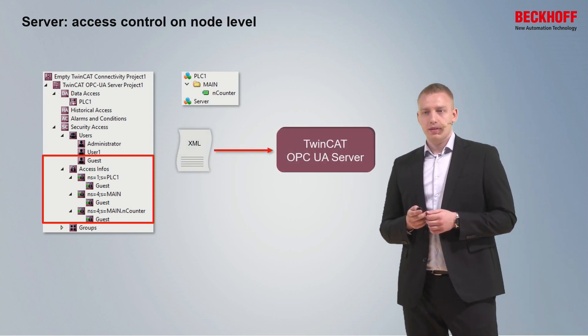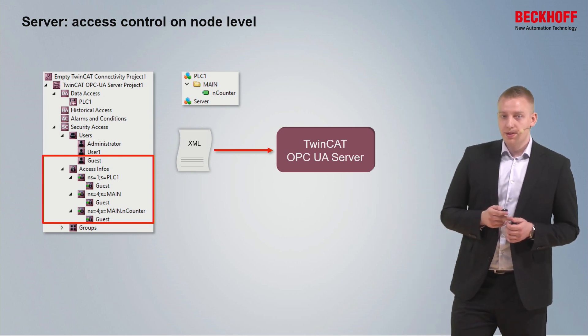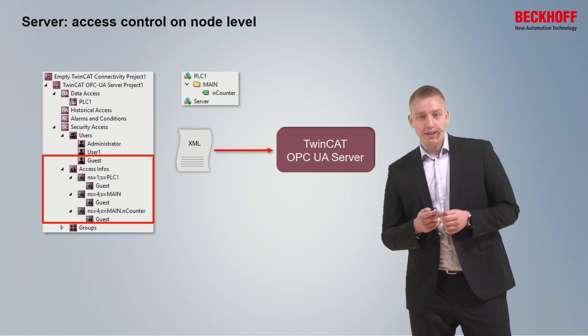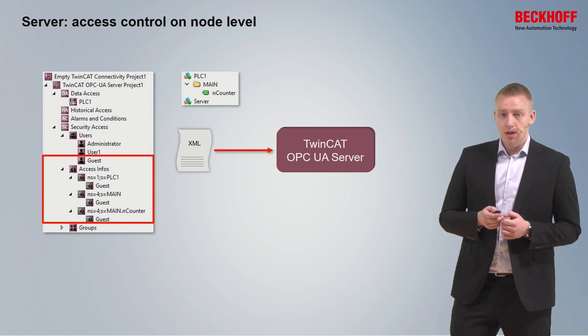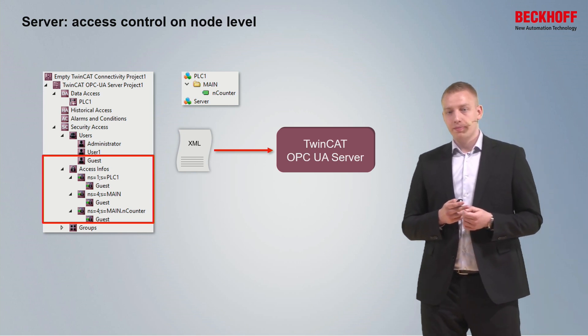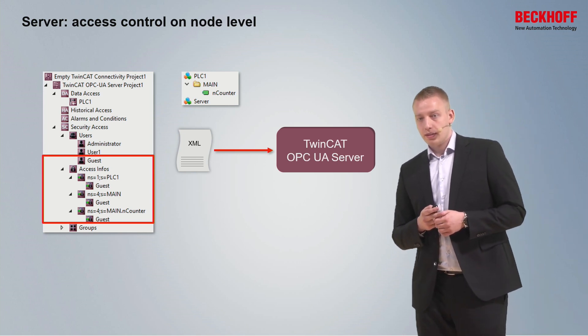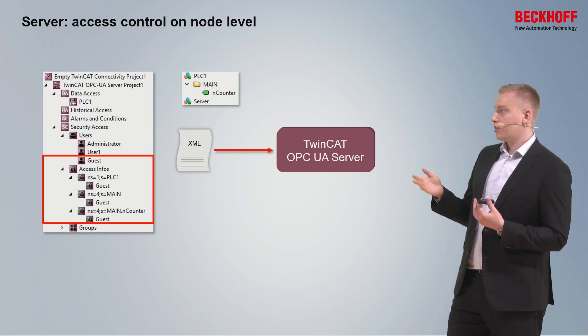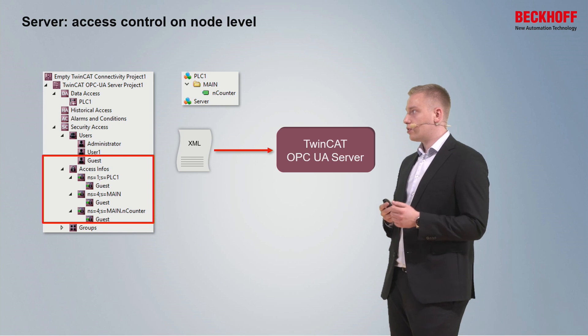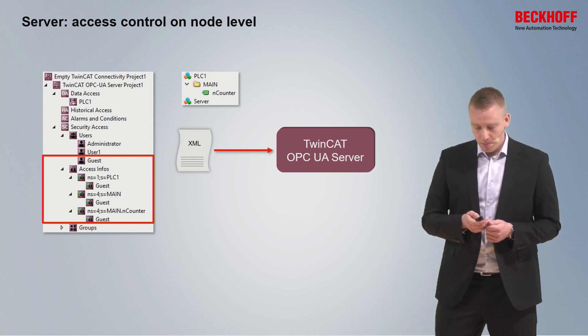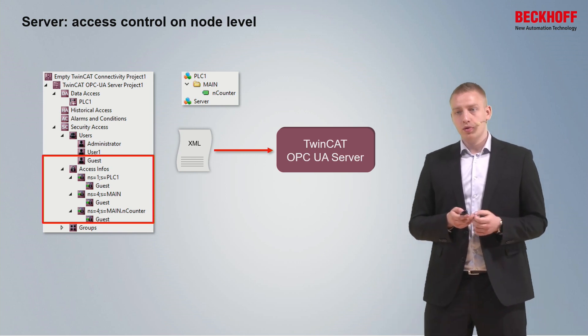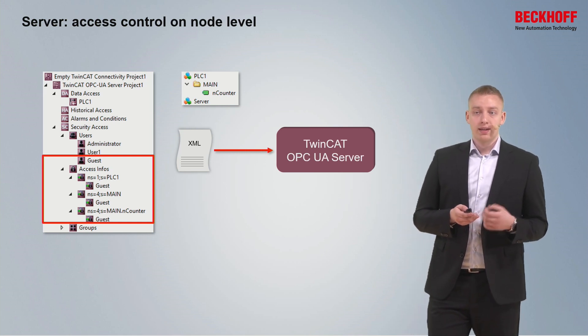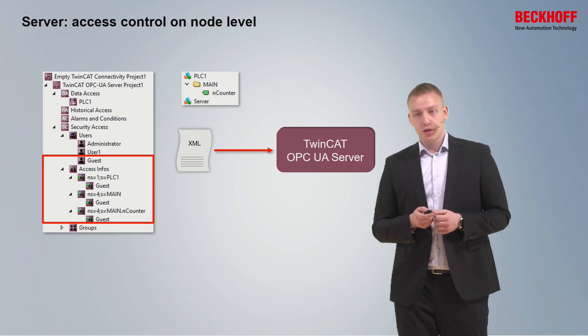Access control on variable level can get very complex with an increasing number of variables and users. Our recommendation is to stay on namespace level with restrictions as long as possible. The security configuration is stored as an XML file — the TwinCAT OPC UA configurator is the UI to edit it, but it is also possible to create and edit this XML file in your own application.